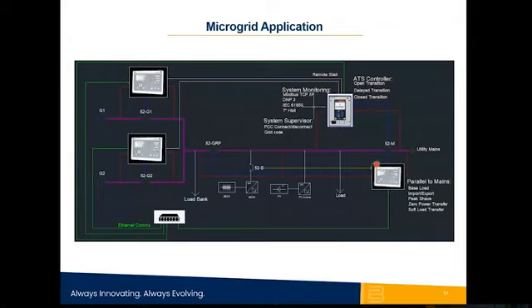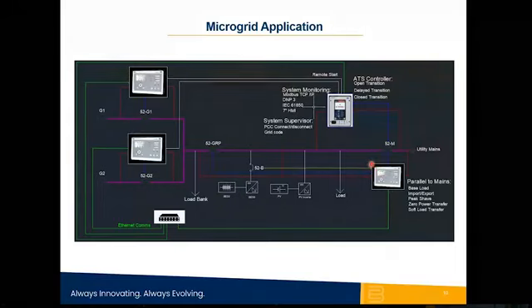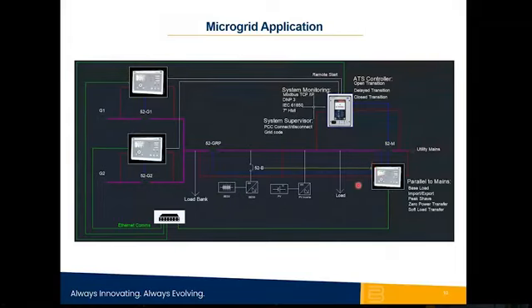Of course, at the point of common coupling, you want to have a utility-grade protection relay. It's going to be doing the connecting and disconnecting, following grid code requirements such as IEEE 1547, and also with the ability to communicate with advanced protocols like IEC 61850 and DNP3, and do other things over Modbus TCP/IP, for example. ATS control is also possible. This is the BE1-Flex, our most up-to-date protection relay, which has tons of capabilities. All of what I'm showing here and more can be achieved with this protection relay.